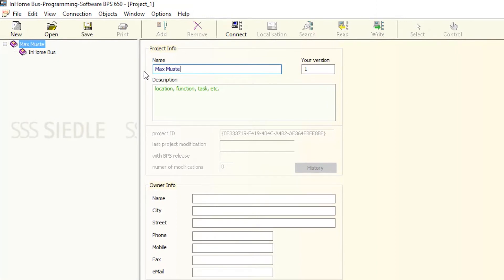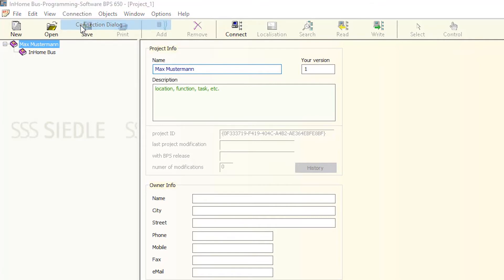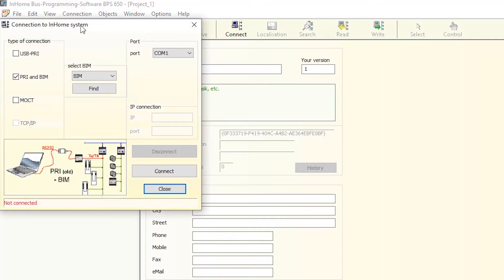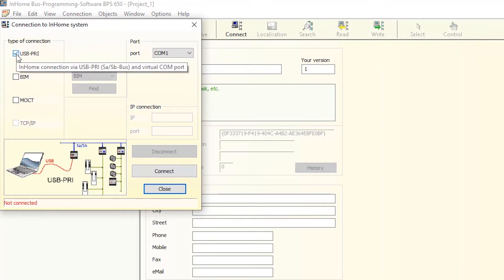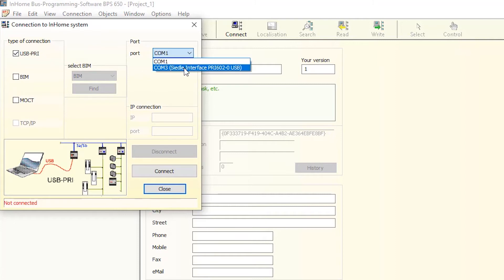Then create a connection to the in-home bus system. Click the Connection tab and select the line Connection dialog. Tick the box for the relevant connection type, in our example USB PRI, and select the COM3 port in the Port section.